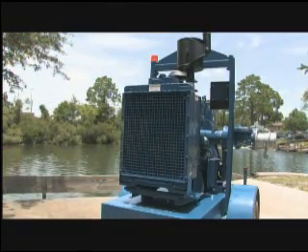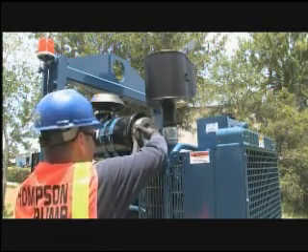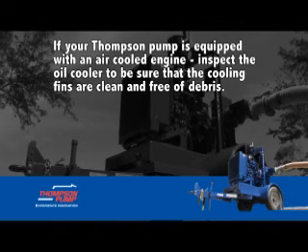The engine oil should be clean and the level should be within the operating range on the dipstick. Verify that the radiator core is clean and free of any debris or residue. If applicable, check the air filter and air restriction gauge and clean the dust port. If your Thompson pump is equipped with an air-cooled engine, inspect the oil cooler to be sure that the cooling fins are clean and free of debris.